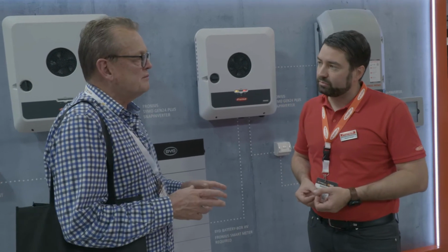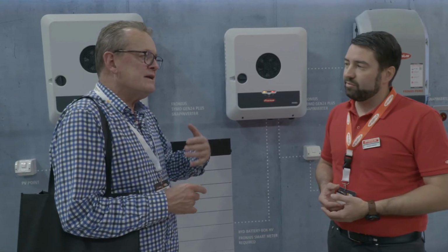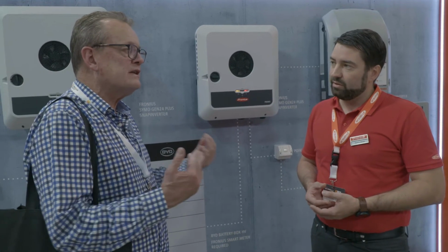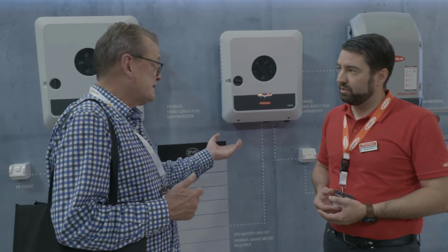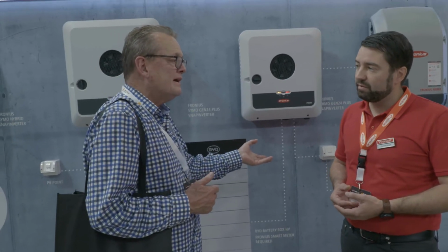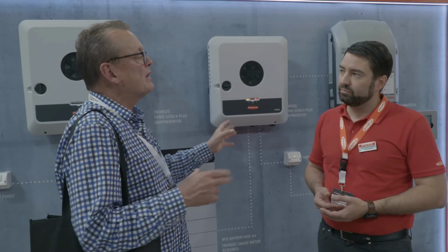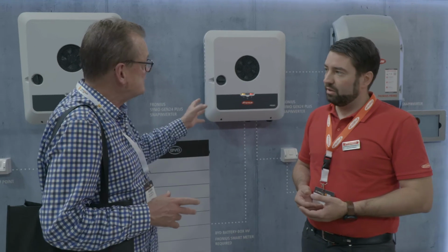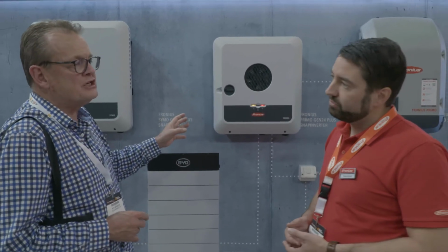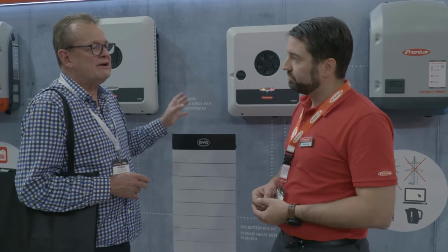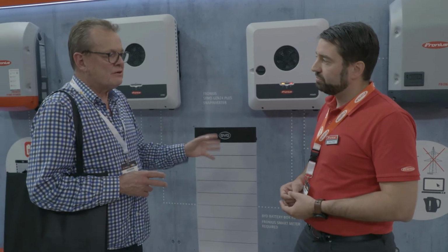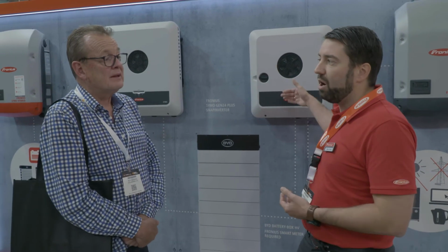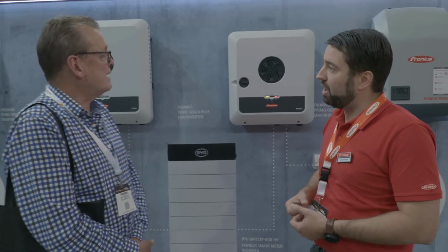And that's quite unique in the hybrid space, isn't it? Because all the other hybrids we've been handling to date are limited to somewhere between 16 and 20 amps—normally 16 amps without battery, or just off solar, and then with solar and battery during the day they'll go to 20 amps. So what you're saying is it's possible to engineer with Fronius a higher amperage delivery without the grid—you can go up to the nominal power of the inverter with the backup power.